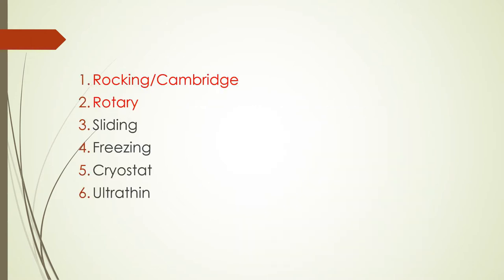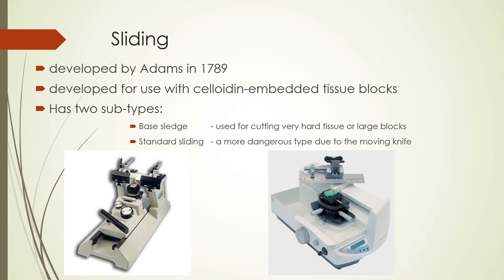Next we have the sliding microtome. It was invented by Adams in 1789, making it older than the rocking and rotary microtomes. It was developed for use with celloidin-embedded tissue blocks and has two subtypes: the base sledge and the standard sliding. The base sledge microtome is used for cutting very hard tissues or large blocks.